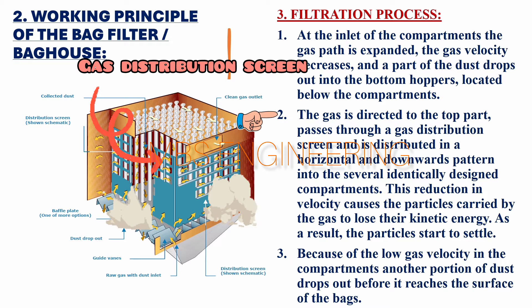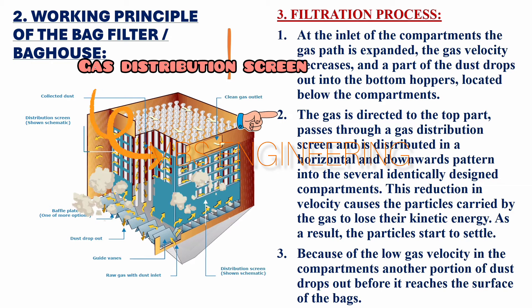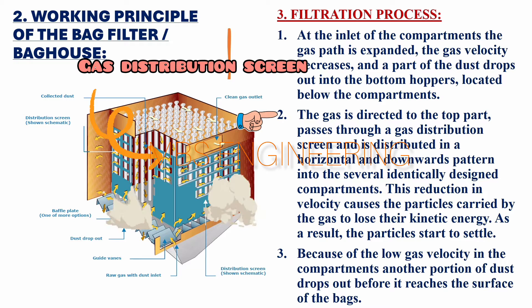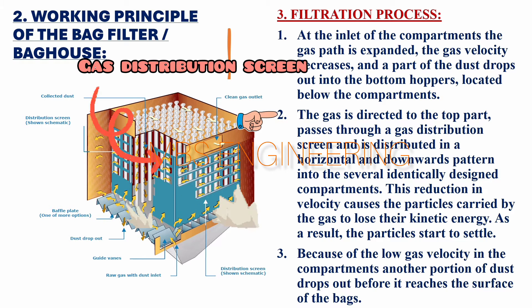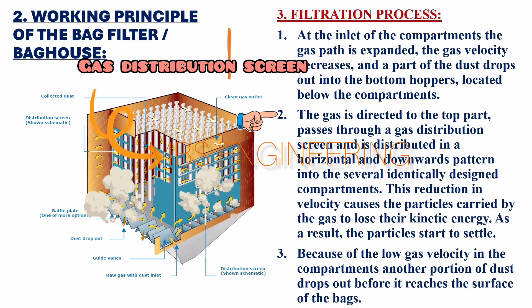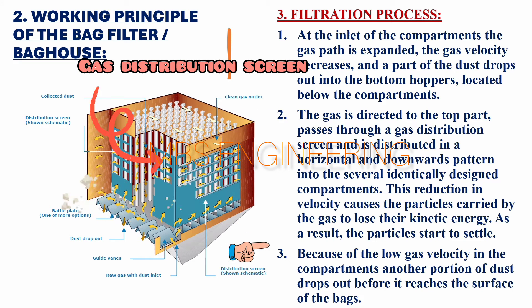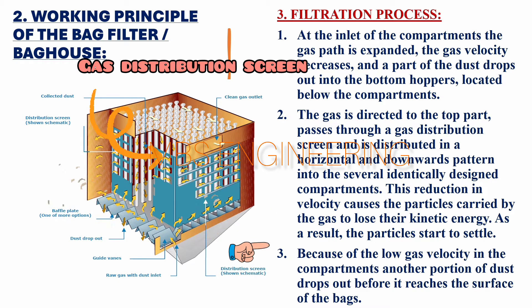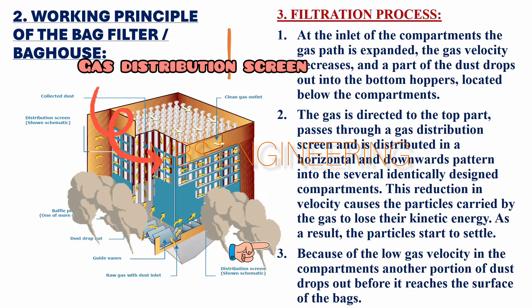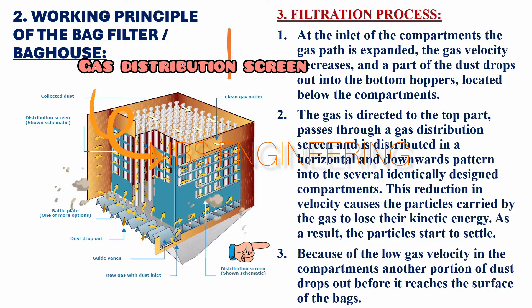The gas is directed to the top part, passes through a gas distribution screen, and is distributed in a horizontal and downward pattern into several identically designed compartments. This reduction in velocity causes the particles carried by the gas to lose their kinetic energy, and the particles start to settle. Because of the low gas velocity in the compartments, another portion of dust drops out before it reaches the surface of the bags. Gas distribution screens, baffle plates, and guide vanes are used to reduce flue gas velocity.